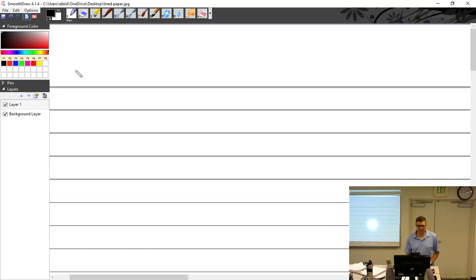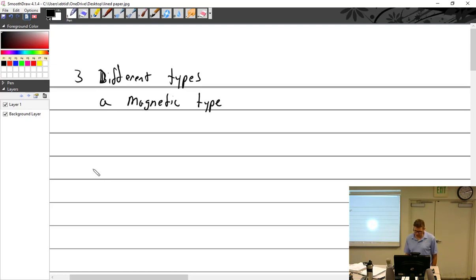All right, I got three different types. We have the magnetic type of circuit breaker. When excessive current flows in the circuit, it makes an electromagnet strong enough to move a small armature which trips the breaker. So without writing all of that, it uses magnetic strength to open. Obviously it's set for a certain amperage.